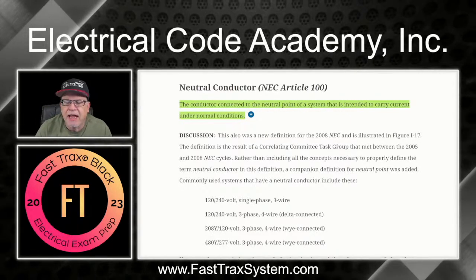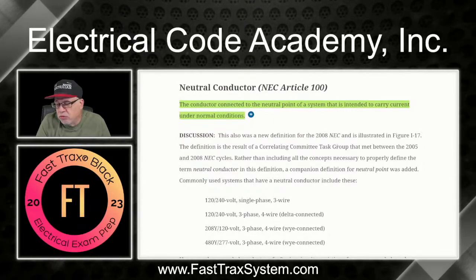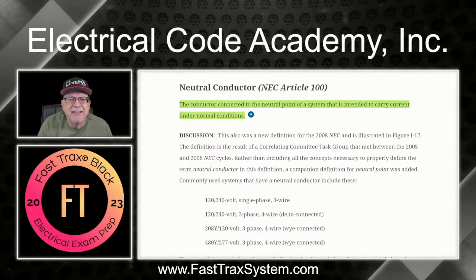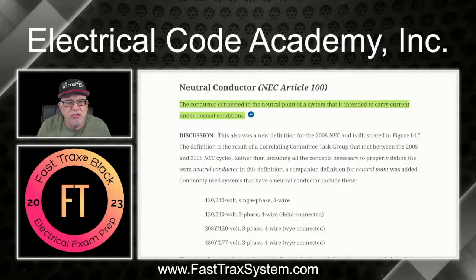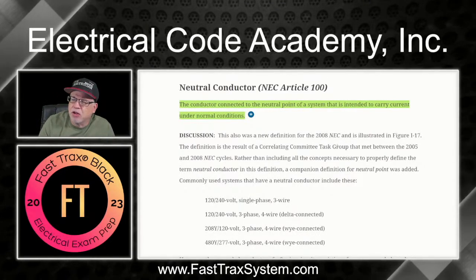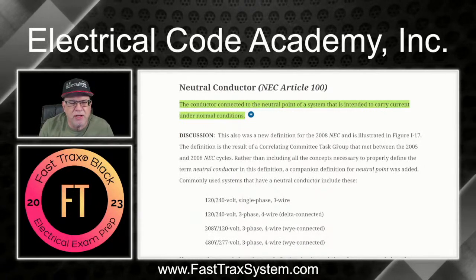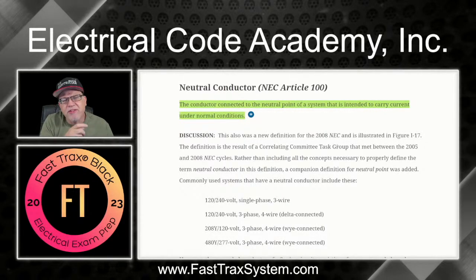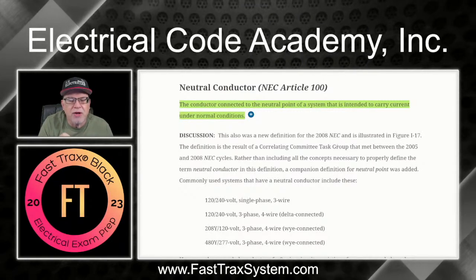In 2008, a correlating committee task group was charged, between the 2005 and the 2008 cycle, to look at the use of the term neutral throughout the NEC. And so they looked at it and said, you know what, we need to come up with a definition. Well, when they came up with that definition, they said, look, we need something else.